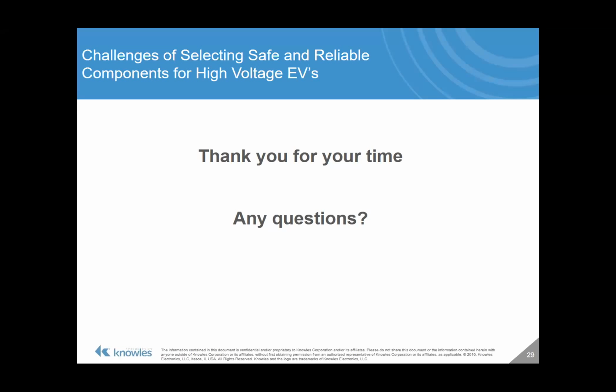So it's not an easy answer. And it's something that you really need to talk to your supplier about. We're fielding questions on this several times a week. We also have a test facility built up where, for certain parts within certain limits, we can actually do this test and apply varying ripple currents and look specifically at the temperature rise that's occurring. So it's a very common question, something we look at, but you really need to talk with us or with whoever your supplier is on each individual specific application and your operating and test conditions.